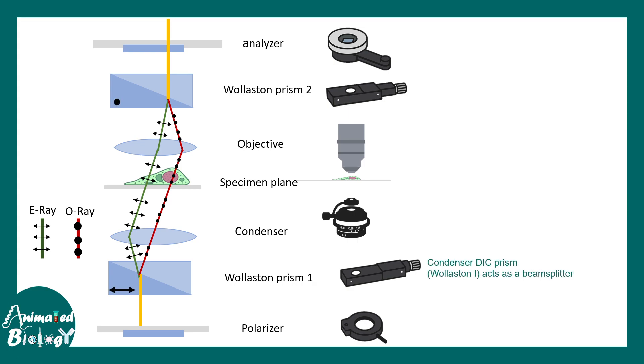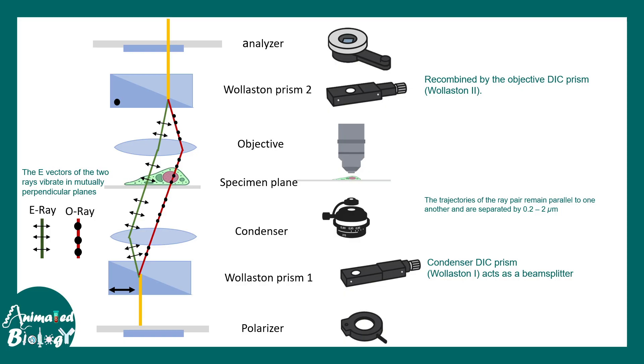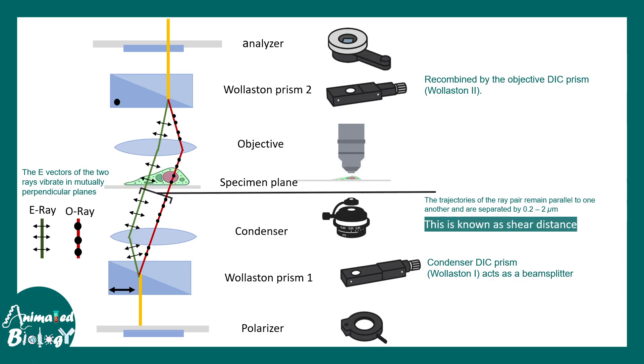The condenser DIC prism acts like a beam splitter, and the objective DIC prism works like a beam combiner. The trajectories of the O rays and E rays — ordinary and extraordinary rays — are separated by 0.2 to 2 microns, which is less than the resolution limit. This distance is known as the shear distance. The smaller the shear distance, the greater the resolution and the crisper the image.